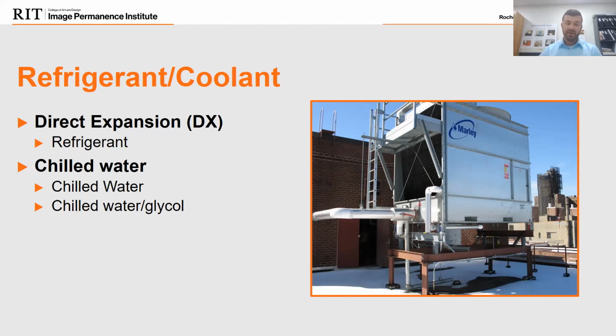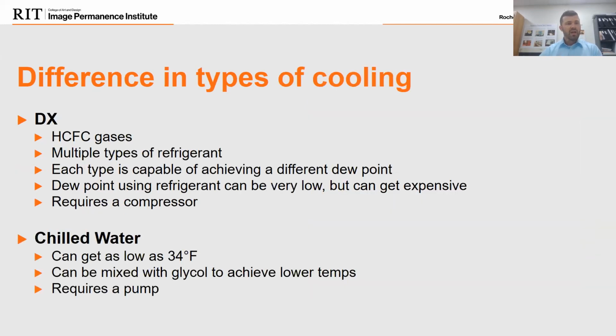It's basically refrigerant. It's what you would typically see in a home air conditioning unit, or what they call a split system unit. Typically that's DX, that's your refrigerant. Or there's chilled water, which is at many institutions. It's a mix of chilled water or chilled water glycol. There's a difference in the types of cooling.